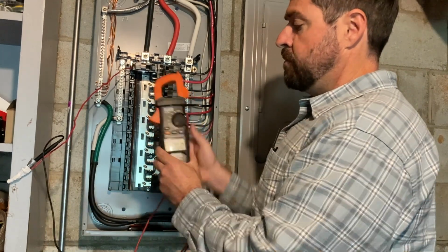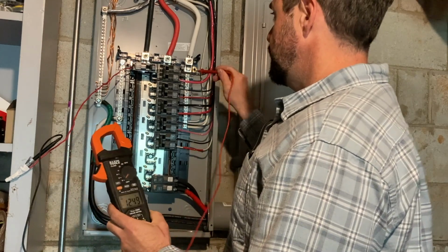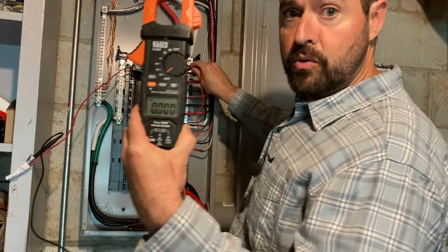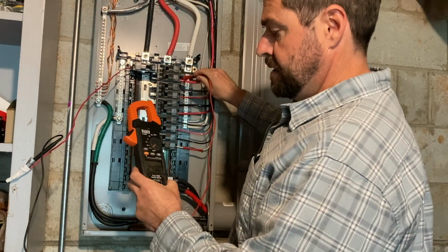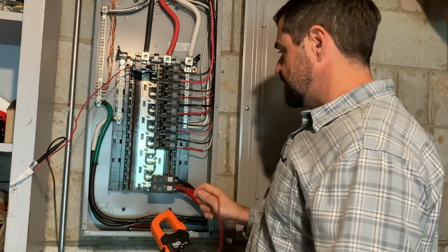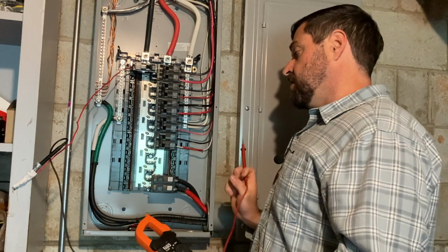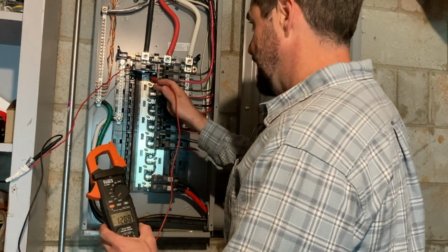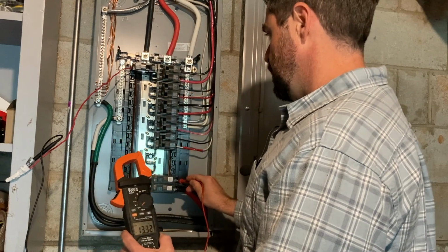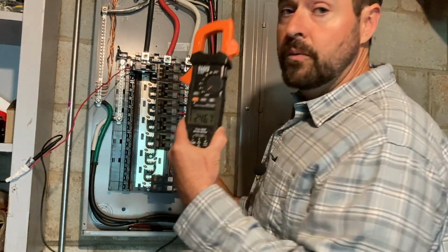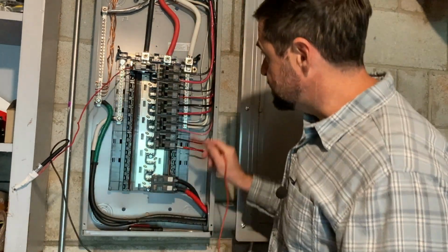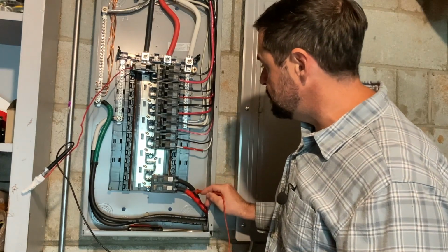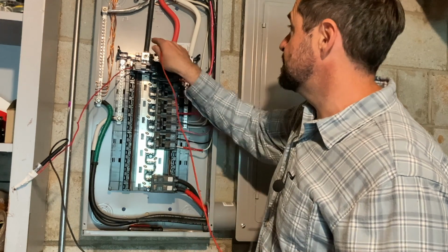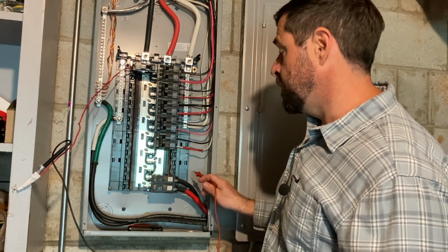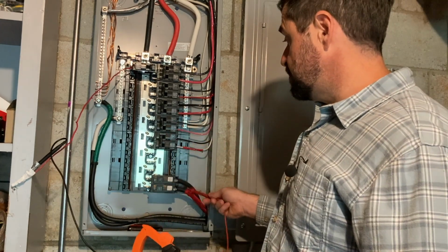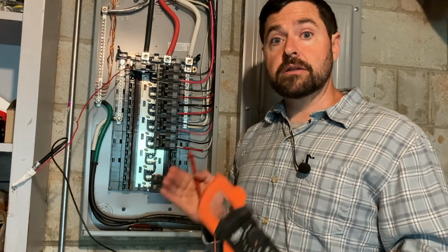You would turn your voltmeter to volts alternating current. And then, if you're on the same lug, you get 0 volts. See that? If you're on the opposite lug, you'll get 240. Now let's just pretend this right here, the sub-feed lug kit, is feeding our backup interface. Black wire, L1 CT. This is L1 feeding the backup interface. Uh-oh, we've got 240 volts. That would mean someone did not pay attention when they color-coded these two wires. The red wire is actually on the same phase as the black wire up here. So, assuming we want to just keep black as L1, we would want to swap these wires to make sure that our phases are aligned.